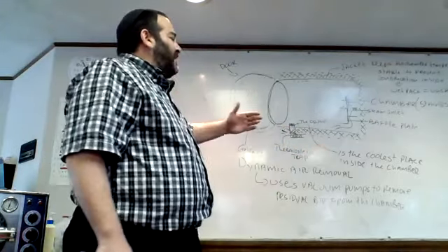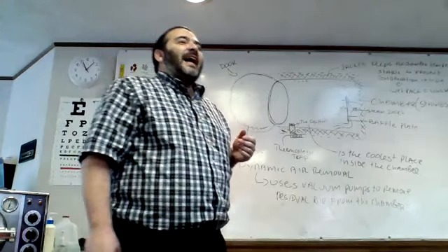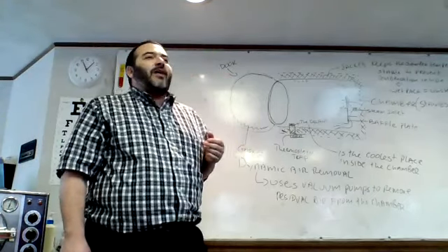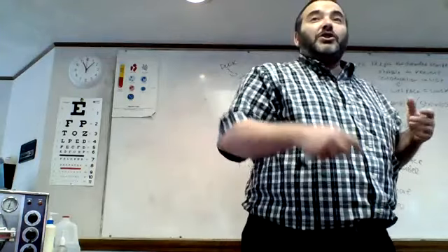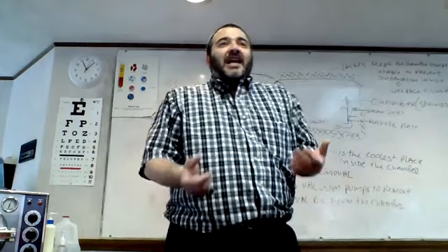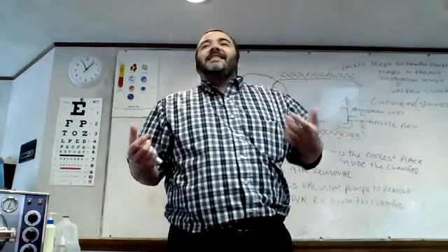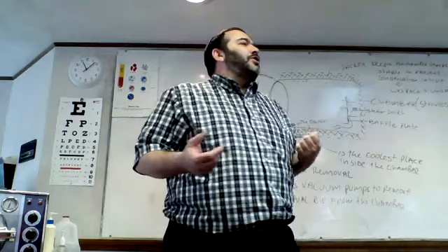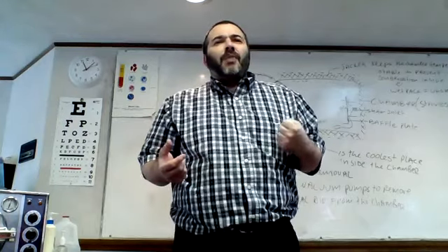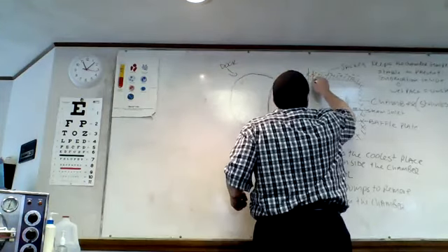So, what is the difference between dynamic air displacement machines and gravity air displacement machines? Well, gravity air displacement machines use just expanding steam, so it's a fully passive cycle. We heat up the water, it turns into steam. Dynamic air displacement, we introduce a new vacuum pump into the mix. So into this picture, we can add one more nozzle. Let's say we put it over here, and we call it a vacuum pump.